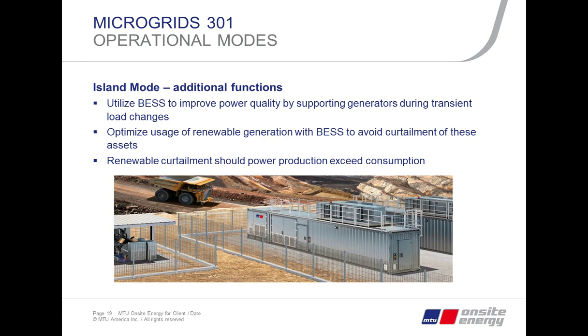You'd typically want a BESS, or battery energy storage system, to improve power quality by supporting the generators during transient load changes, especially with gas generators, which don't load up as quickly as diesel. A battery smooths that transient and keeps power quality where it should be. Also, since there's no grid to export excess renewable power to, we want the battery storage available to absorb power from solar or wind when there isn't enough load on site, since we don't want to curtail the renewable resources. We'd rather store that energy in the battery, and that's one of the key focuses of the intelligence here, to avoid curtailment in island mode.